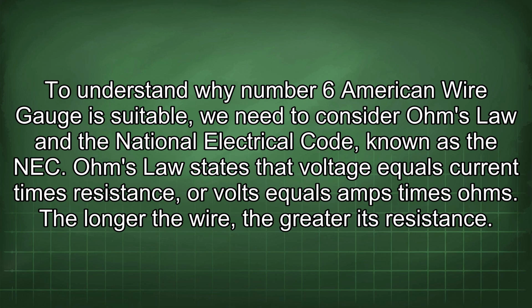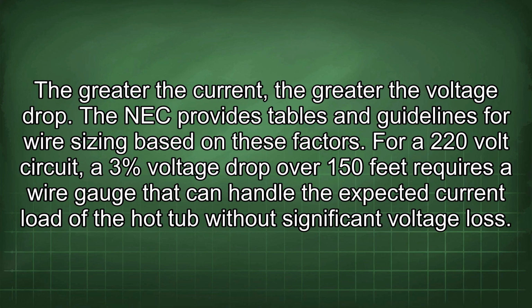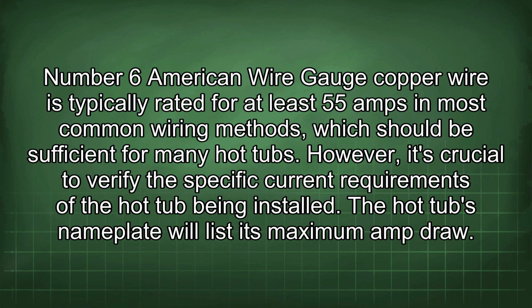Ohm's law states that voltage equals current times resistance, or volts equals amps times ohms. The longer the wire, the greater its resistance. The greater the current, the greater the voltage drop. The NEC provides tables and guidelines for wire sizing based on these factors. For a 220 volt circuit, a 3% voltage drop over 150 feet requires a wire gauge that can handle the expected current load of the hot tub without significant voltage loss. Number 6 American wire gauge copper wire is typically rated for at least 55 amps in most common wiring methods, which should be sufficient for many hot tubs.